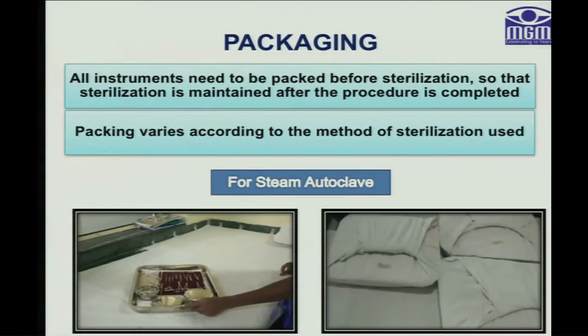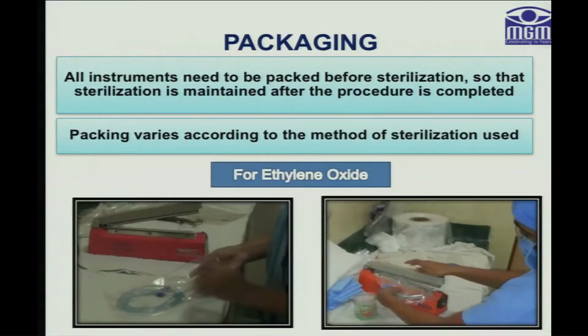Packaging: all the instruments need to be packed before they undergo sterilization so that the sterilization is maintained after the procedure is completed. And the packing varies depending on the method of sterilization used. For steam autoclave, the instruments are placed in the trays and then covered with cloth, and then it is placed inside the autoclave. For ethylene oxide, the instruments are placed inside the plastic bags and then sealed.